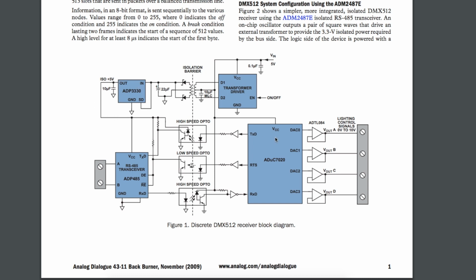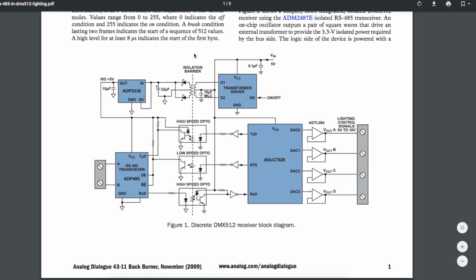And likewise, any data coming across the barrier in either direction will go through opto-isolators. So if this right side is some expensive equipment, and the left side has this communication data cable running for a long distance, and it can pick up all kinds of noise or even have voltage and current spikes on it, this isolation barrier helps keep everything clean on the receiver side and anything harmful over on the outside world.